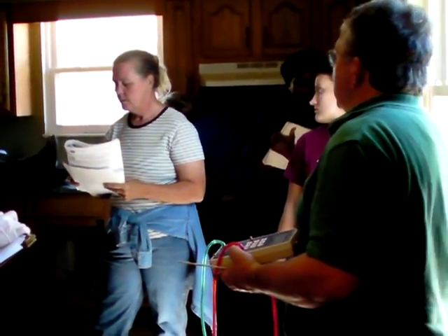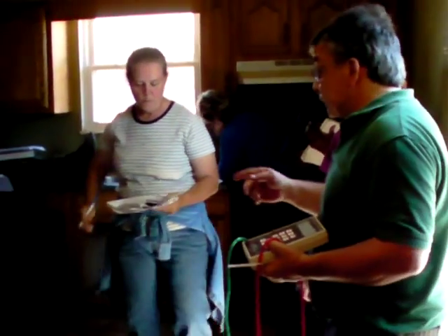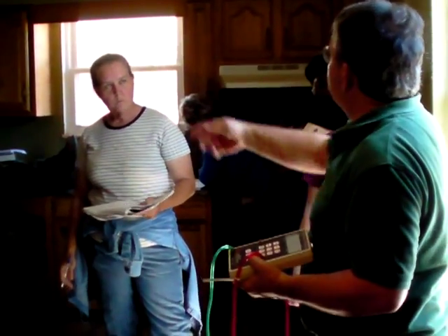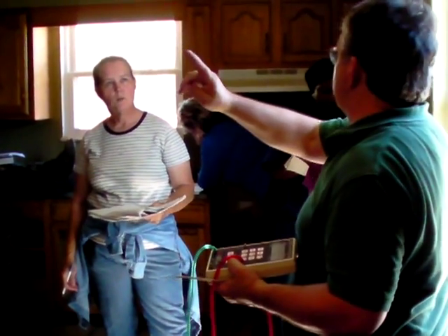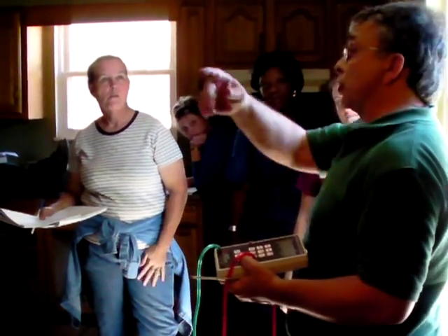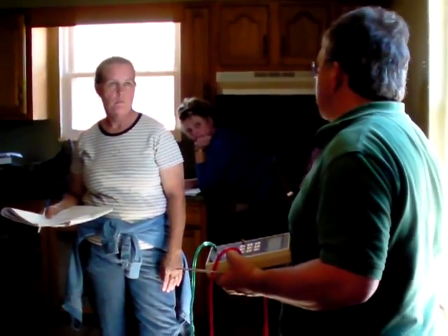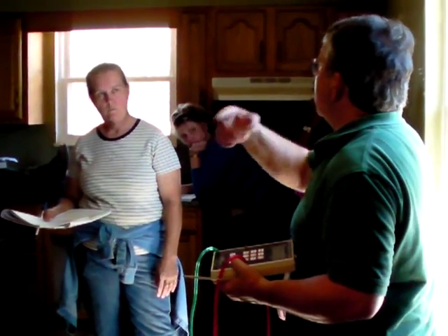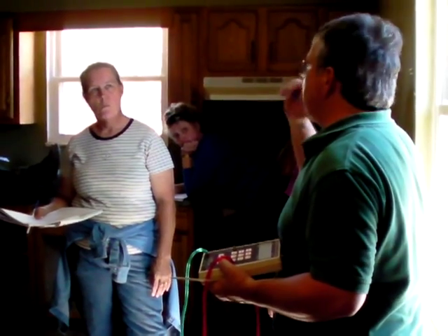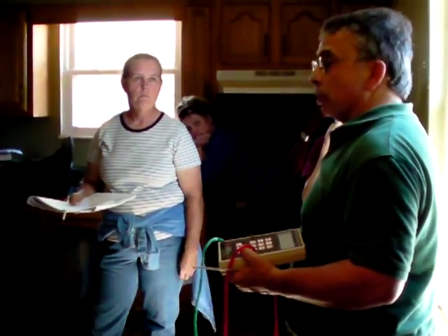That's right. Okay. Now here's a little piece of info that I neglected to tell you when we were doing this dominant duct leakage test: in a house like this where I have a common return, what I really should have done to do that test well is, I should have shut those bedroom doors back there, because by cutting off the supplies to those rooms, that's the same thing as making my return stronger. Did you see that? It can't get back to the return, so it's not going to have to suck as much. It's going to make it stronger.